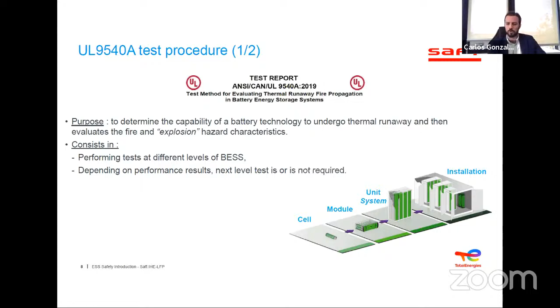So, in the core of the design, the most known standard globally is UL 9540A, which is the market practice standard for these systems. You can test it at a cell level, a module or unit level, and an installation level. In the end, this test is looking to see if a thermal runaway can occur, and also what the fire and explosion hazard characteristics are. I'm not going to go into detail here, as this could be a whole webinar on its own, but this is the market minimum practice, requested in most markets.